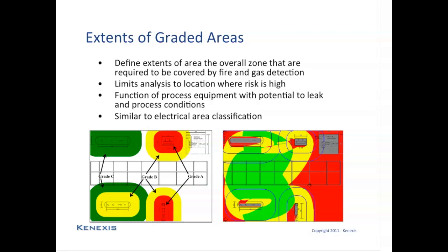So the philosophy document that an organization generates is going to need to define not only how areas are graded, but also what the extents of the graded areas are geographically in relation to the leak sources that are present. Then when a geographic coverage is performed, you only calculate the coverage of the graded area, not the entire zone. This will prevent you from analyzing areas where there is no risk, because those areas would be ungraded, or in the drawing below, they would be white.